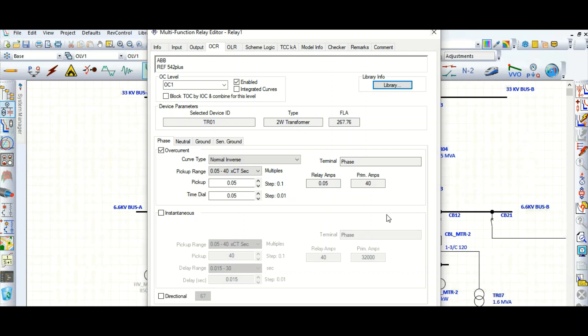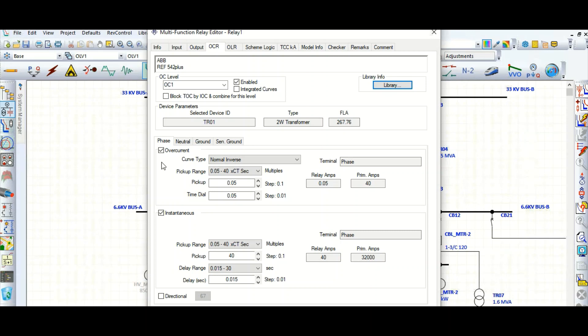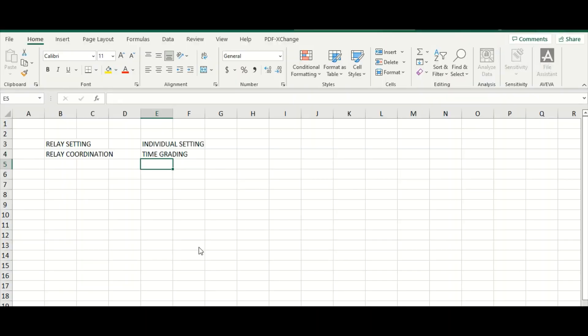I have come back with protection coordination setting. I'm talking about 51 and I will also include 50, which is instantaneous. What are the parameters required to define the 51 element, which means IDMT relay element. This is IDMT overcurrent for phase, and for instantaneous, which is 50.